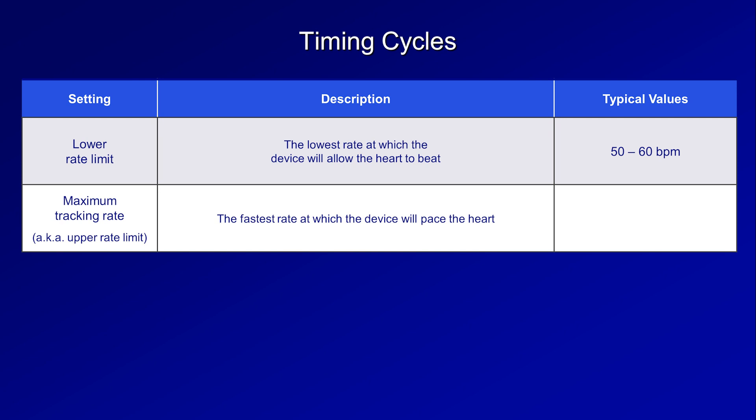The converse to the lower rate limit is the maximum tracking rate, occasionally called the upper rate limit — the fastest rate at which the device will pace the heart. Typical values are 120 to 130 beats per minute, though higher rates might be used in middle-aged or younger patients. Tracking refers to the process by which a pacemaker paces the ventricle at the intrinsic atrial rate, so if the atria beats faster, the pacemaker paces the ventricles faster in a 1-to-1 ratio, up until the maximum tracking rate is reached.